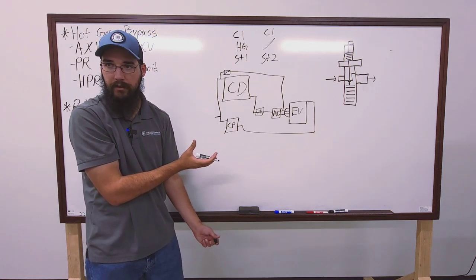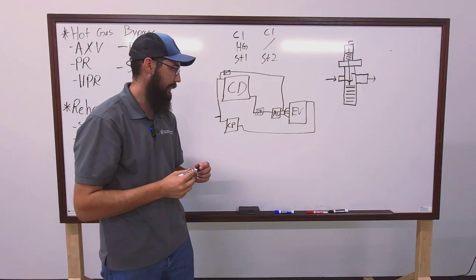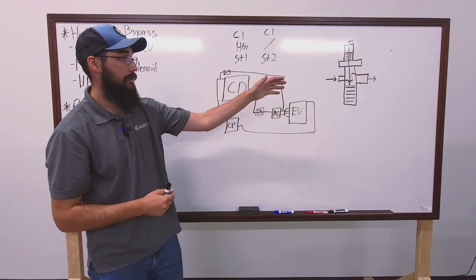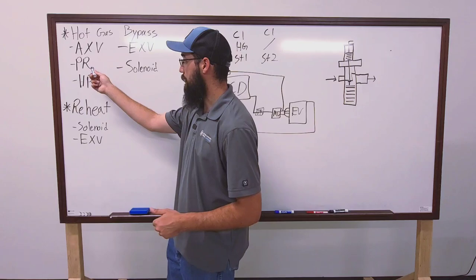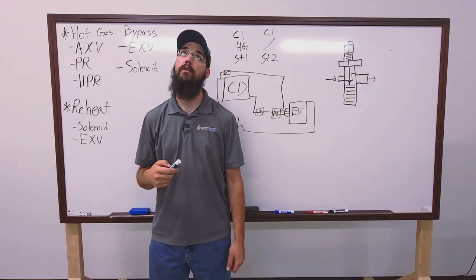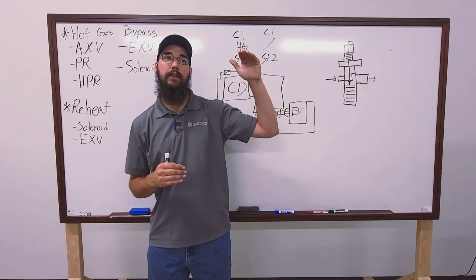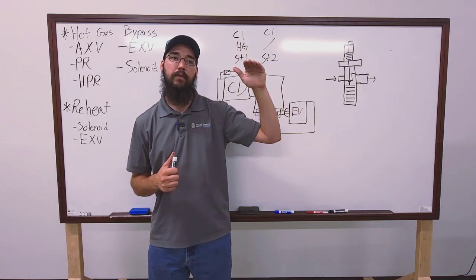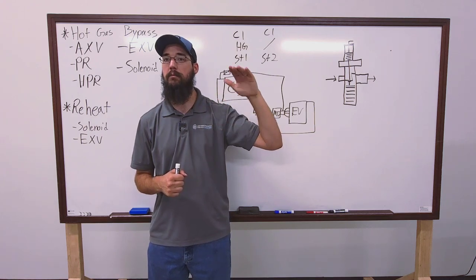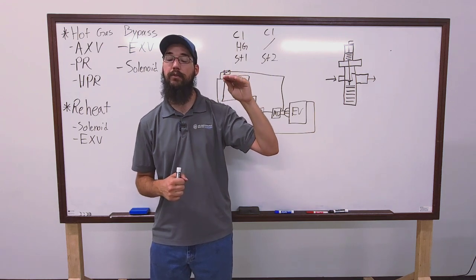I mean, a few feet's not that big a deal, ultimately. Yeah, that's what you're considering the lines are on most of these. Right. But that's what can happen. It's not a guarantee, but it can. So, yes, AXV, automatic expansion valve. They're pressure differential devices. And a pressure regulator is a lot more, ultimately, their main function, it's about differential pressure, but you're really setting the... You're setting a set pressure. You want your evaporator to stay above X pressure. And they act a lot more specific to that pressure, typically.